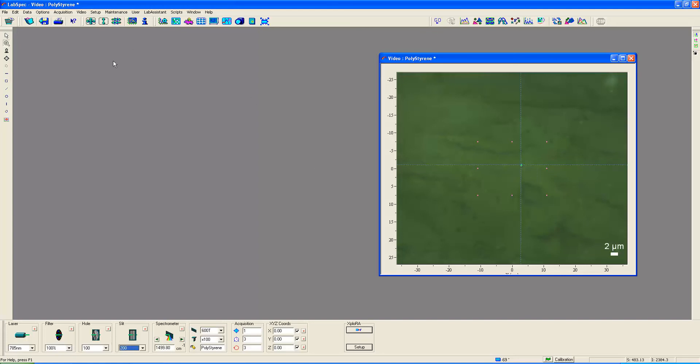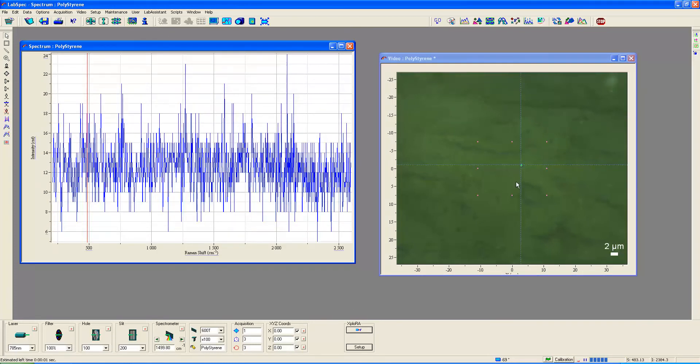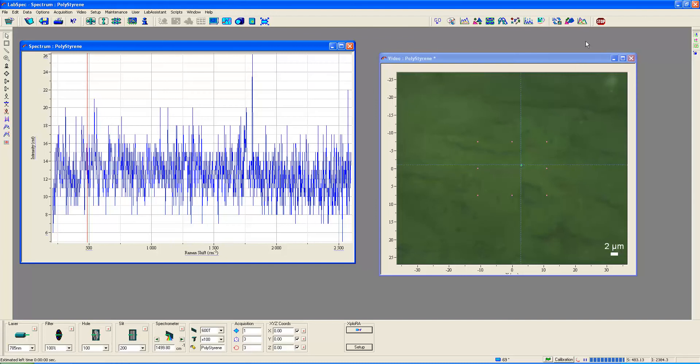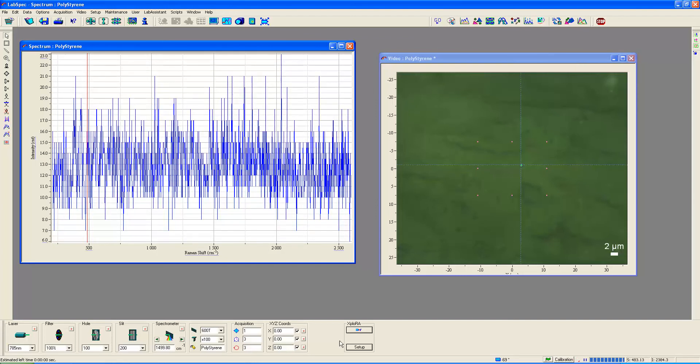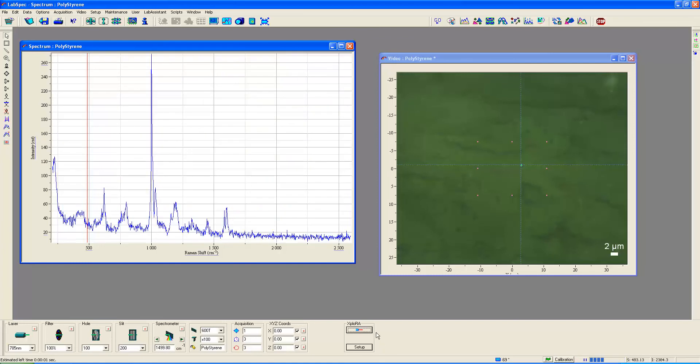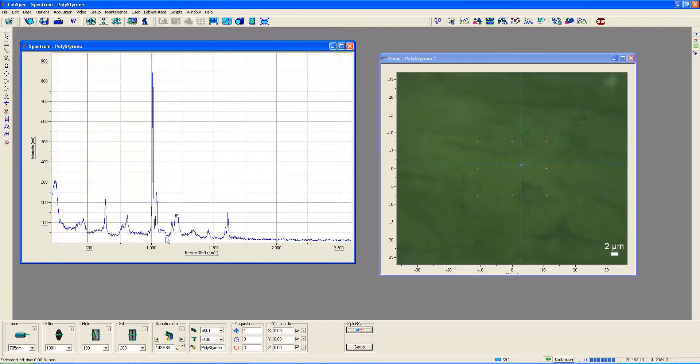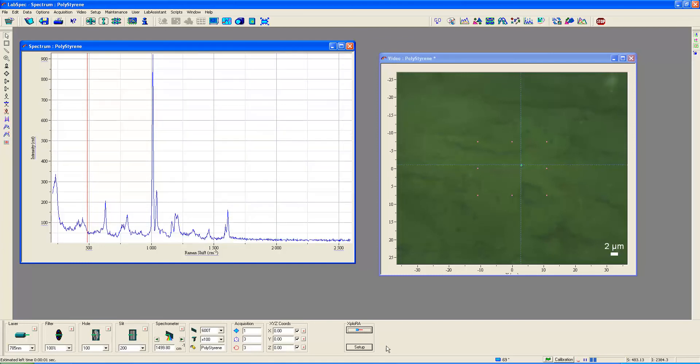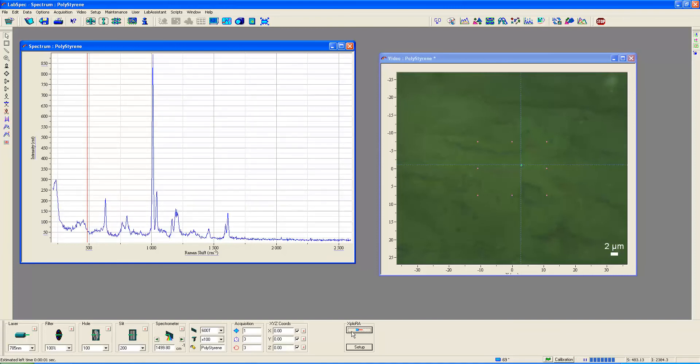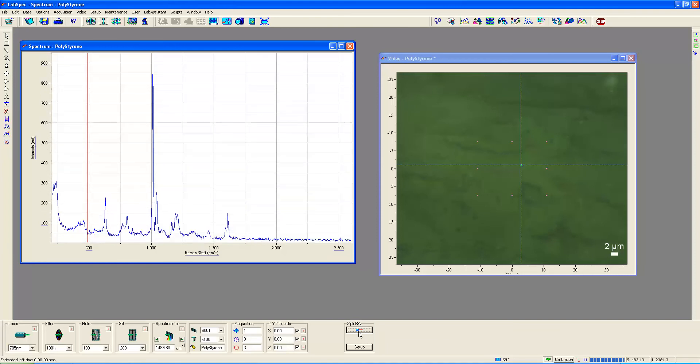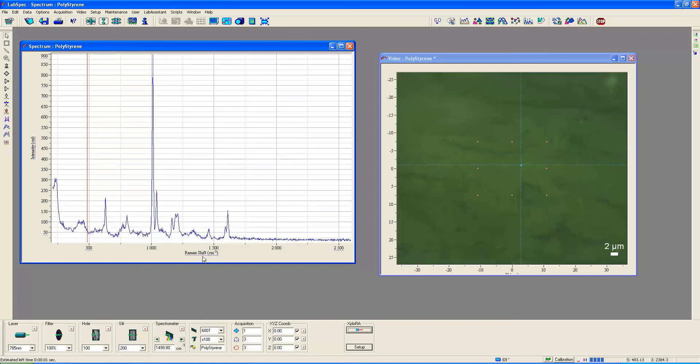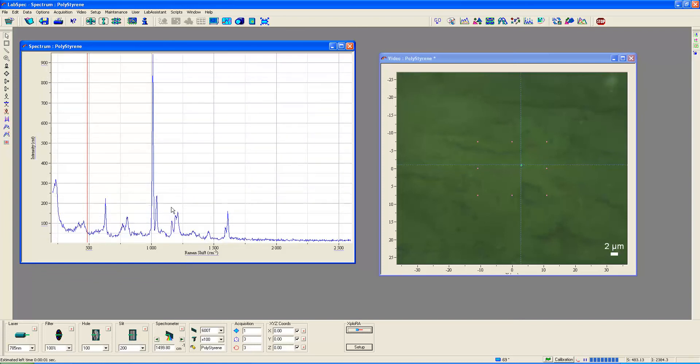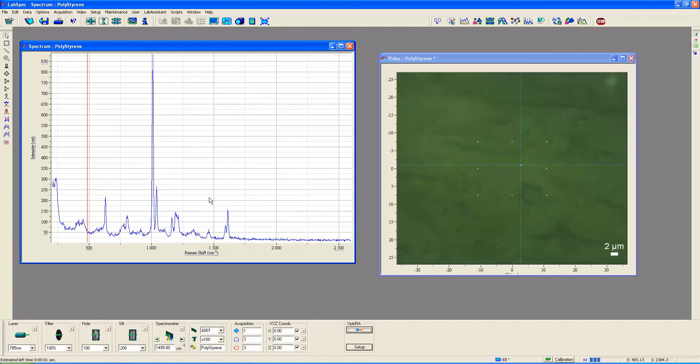Let's take a look at a real-time display with the beam currently focused on the surface. Notice I had been in the video mode, but I had stopped that, and now I go to real-time display, and I don't get a signal. Well, that's because I don't have the laser on. As you see now, if I click on the laser, there's our spectrum. This is a common mistake that people will make. Many of us still do. But always check to see that the laser is illuminating the surface. So now, as you see, we get a very nice real-time spectrum of polystyrene.